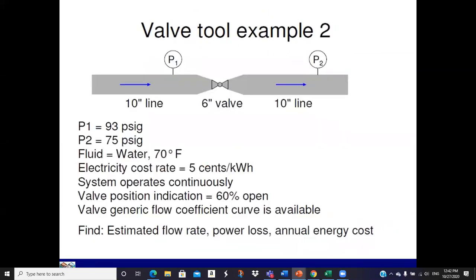So here's another example. We had 10-inch pipe, 6-inch valve. We've got our pressures, water, and all this operates continuously. The valve position is indicated at 60% open. A generic valve flow coefficient curve is available, so we have a curve. So estimate the flow rate, power loss, and annual energy cost.